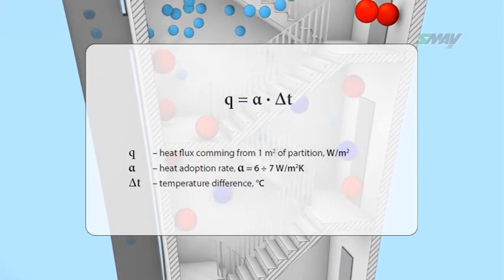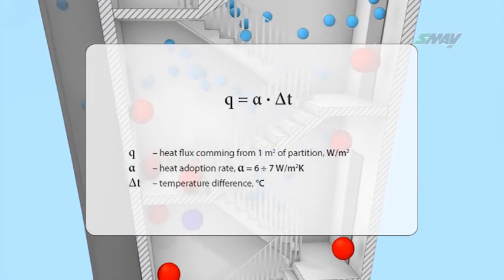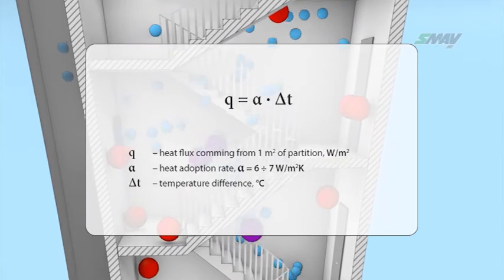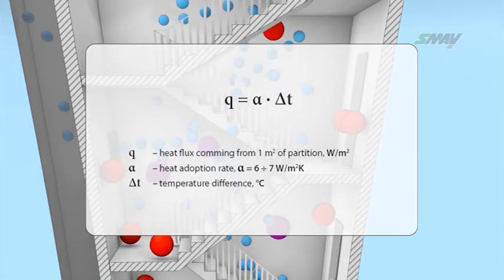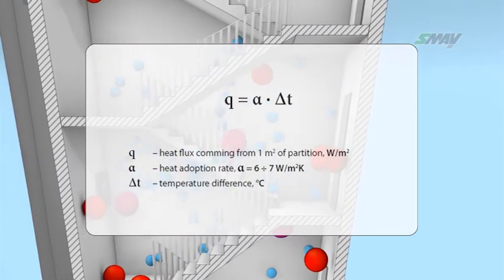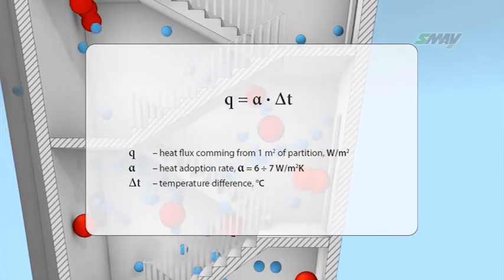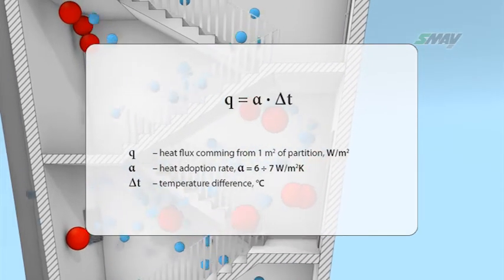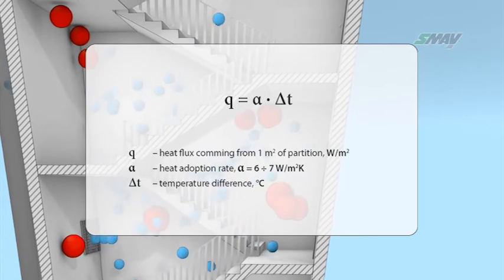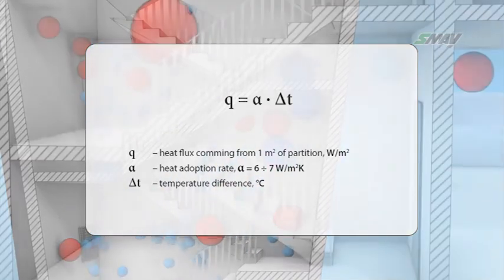For example, if the temperature difference is 20 degrees, the walls may dissipate up to 140 watts from every square meter, as a result of which air density falls, causing buoyancy to push it upwards. We are not talking about serious stairwell heat loss during evacuation as its accumulated heat amounts are vast.